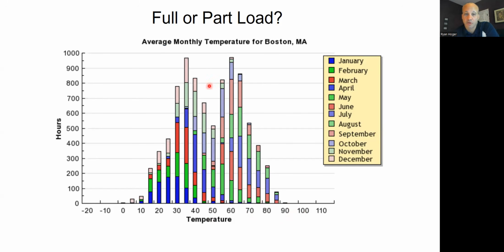So this is how many hours, I don't know if I showed you something similar to this previously or not, but this is how many hours we run at different points of the year. So if I just look at between 80 and 85 degrees, that band of 5-degree outdoor air temperature, let's just call it 250 hours a year are in those 5-degree bands. Whereas if I look at 60 to 65, way up here, I got 950 hours, right?